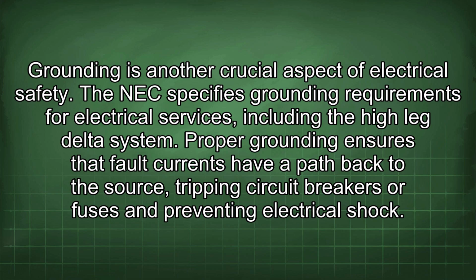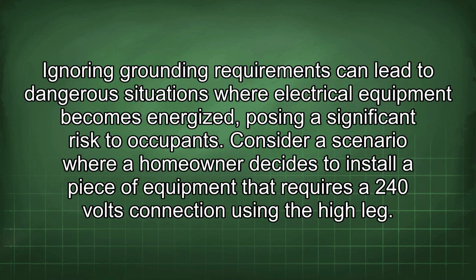Grounding is another crucial aspect of electrical safety. The NEC specifies grounding requirements for electrical services, including the high leg delta system. Proper grounding ensures that fault currents have a path back to the source, tripping circuit breakers or fuses and preventing electrical shock. Ignoring grounding requirements can lead to dangerous situations where electrical equipment becomes energized, posing a significant risk to occupants.